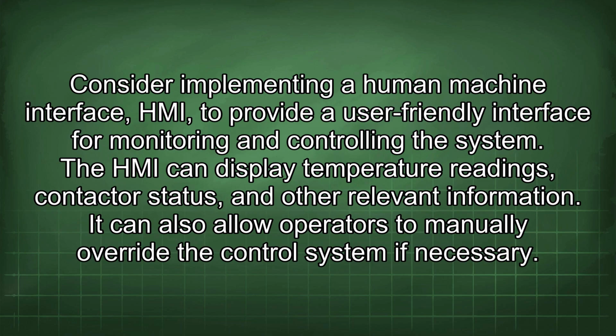Consider implementing a human-machine interface (HMI) to provide a user-friendly interface for monitoring and controlling the system. The HMI can display temperature readings, contactor status, and other relevant information. It can also allow operators to manually override the control system if necessary.